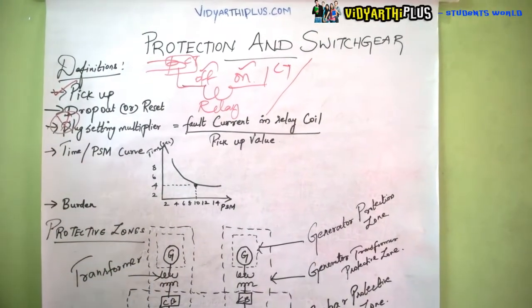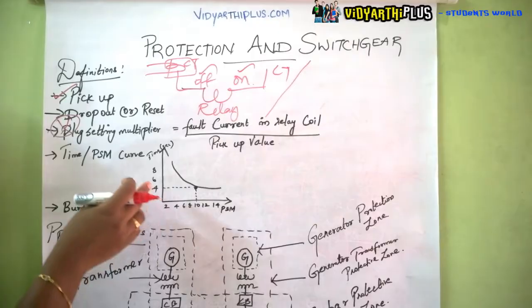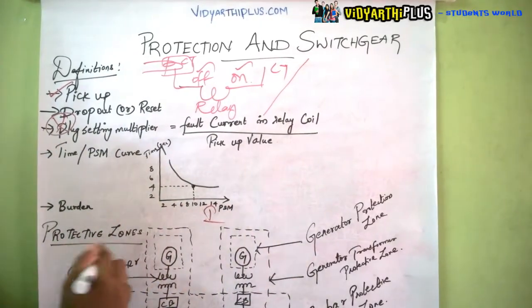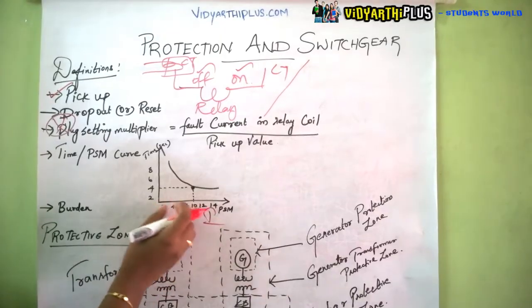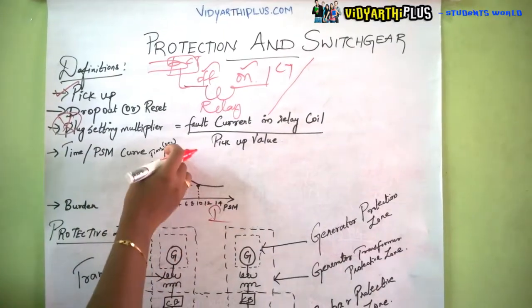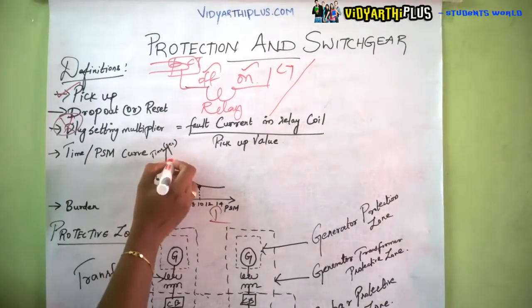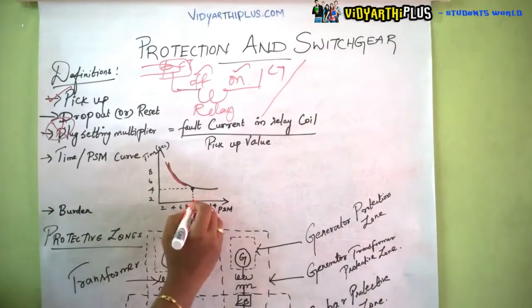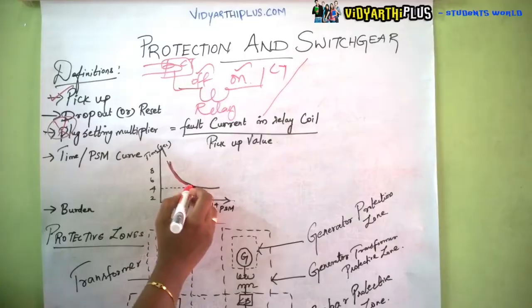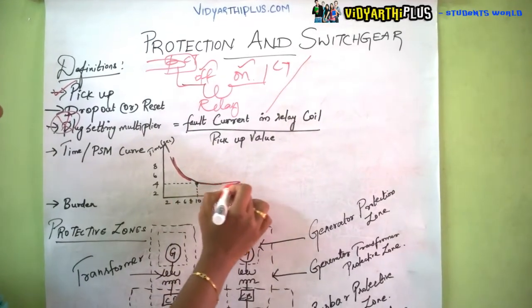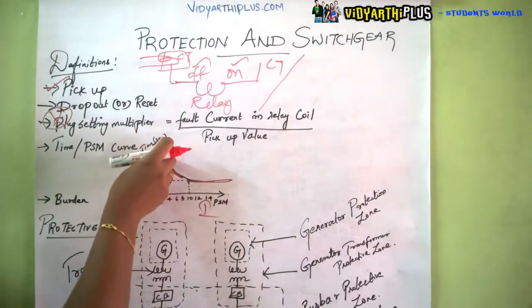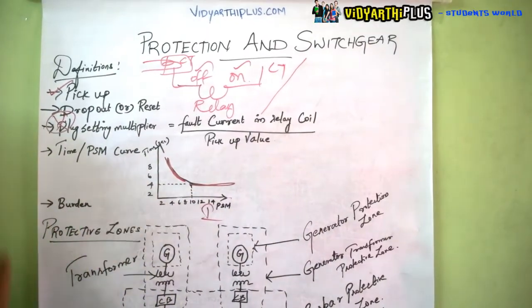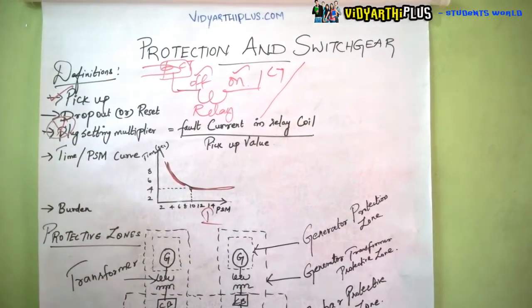Next is the time versus PSM curve, which is drawn between time and current. In the initial stage, time and current are inversely proportional. As the current increases, the time becomes constant. So first it is inversely proportional, and finally it becomes constant — this is the time/PSM curve.